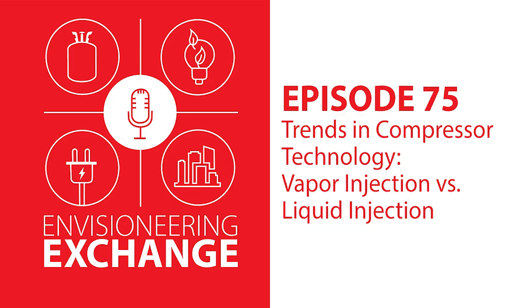But the difference with liquid injection is that you don't get the same benefits as with vapor injection. You don't get the system efficiency improvements because you don't have the secondary heat exchanger in there, and you don't get any capacity boost. It's a simpler system in terms of its architecture because you don't need those extra components. But as we see the market moving, energy efficiency is always going to continue to progress, and you just get more benefits out of vapor injection. So we're seeing a move away from traditional liquid-only injection compressors to vapor injection.